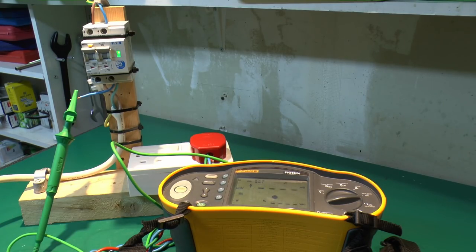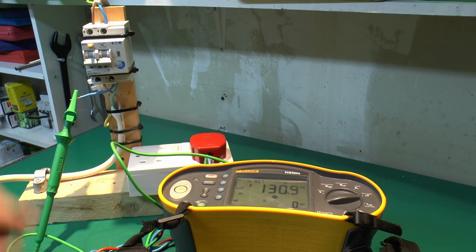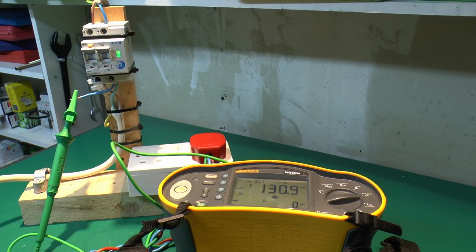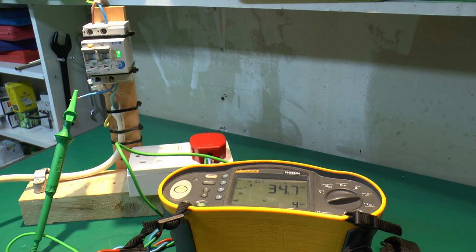Now the first two tests shouldn't trip at all, then we should have four which do, and then we can just look at the times once we've finished. So get that underway. So that'll find that this one should trip, which it does. Just reset. These are the times 5. And this should then stay on completely, and as we see the indicators come on as we had before. So that part of it certainly is functional.